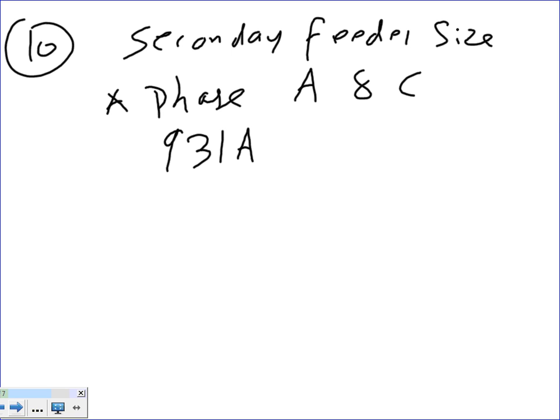93.1 amps, 931 amps. If you take this to table 310.16, why did we go to 310.16? Because it's a low voltage cable. Which column and why? It's over 100. Which column and why, one more time? 75, 90 with the rate.